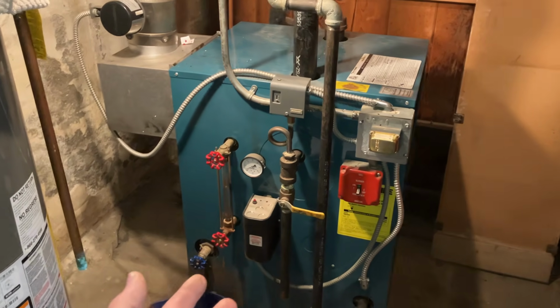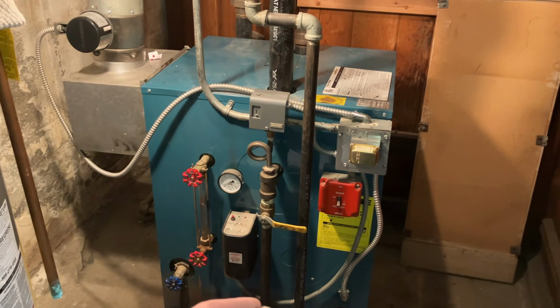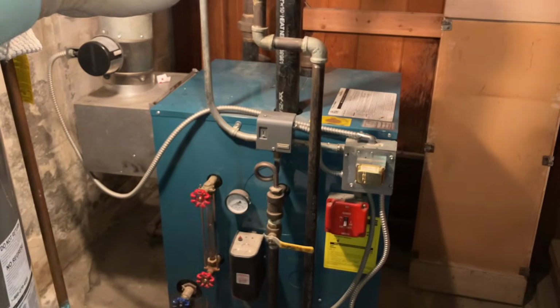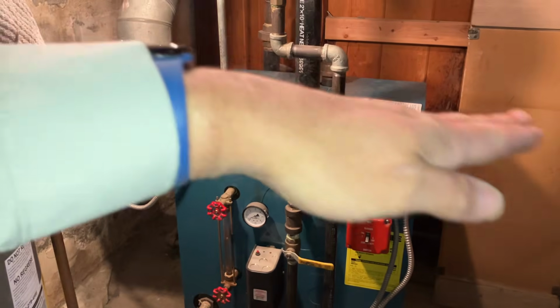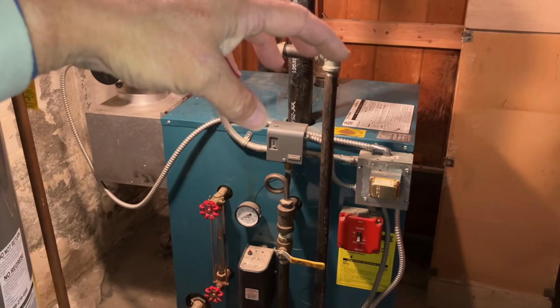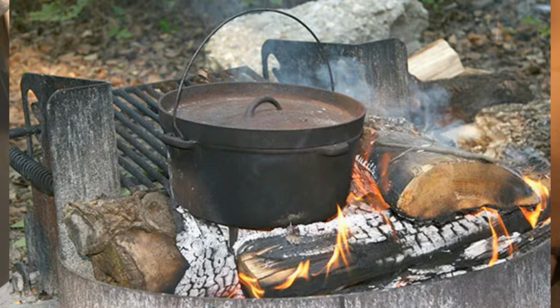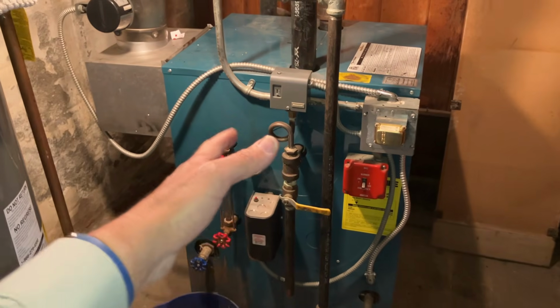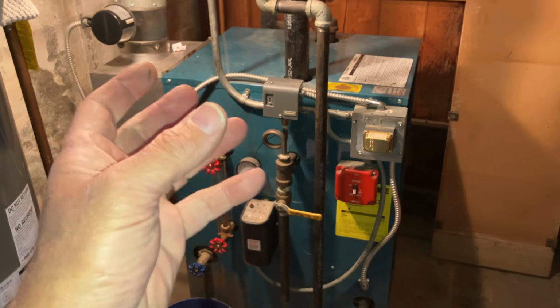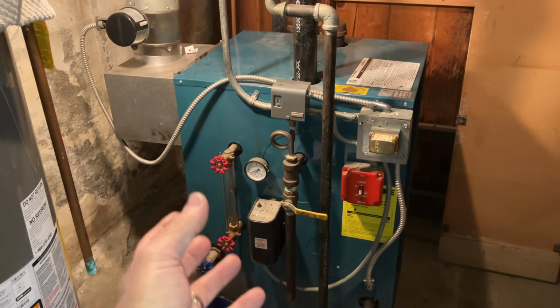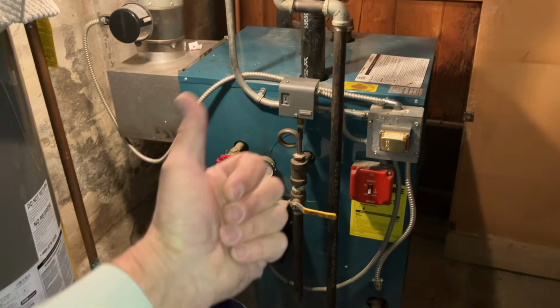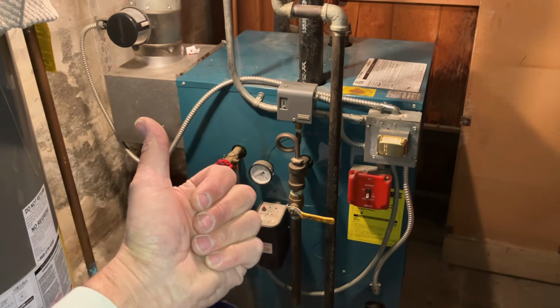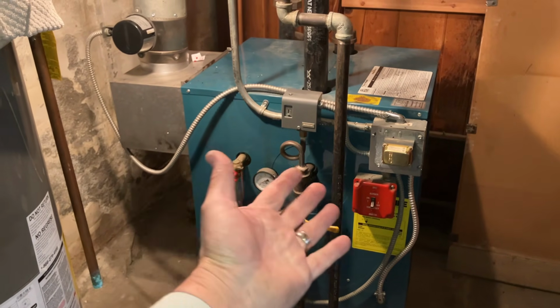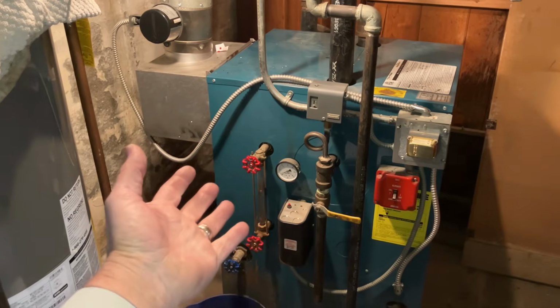And what that is, to put things into layman's terms, you take a match and you put a piece of metal on top of it. You know how the blackness forms, soot forms on that piece of metal? It's like in a campfire, you got your skillet in the fire and you get that black carbon or soot forming on it. Well, when you have incomplete combustion, you're going to get not only carbon monoxide, but the possibility of carbon or soot forming on metal surfaces.